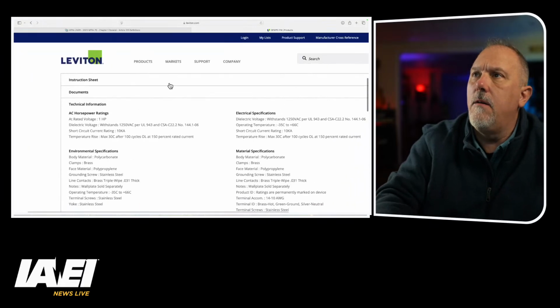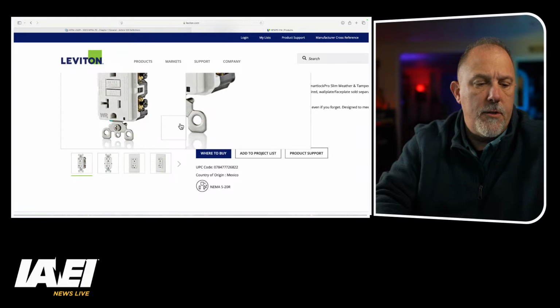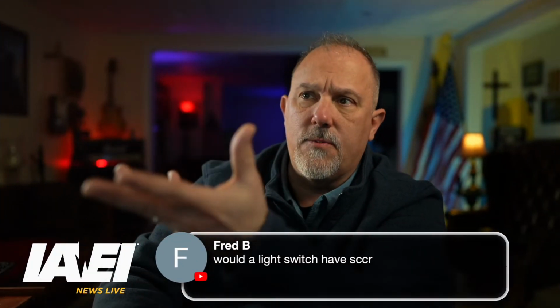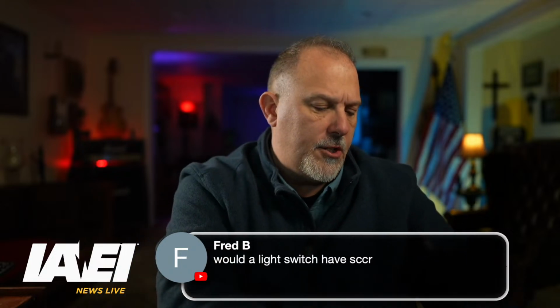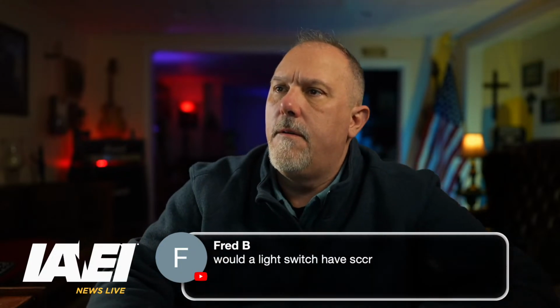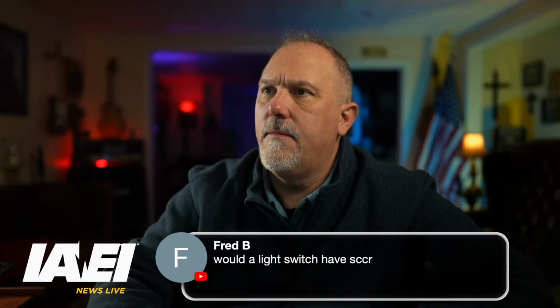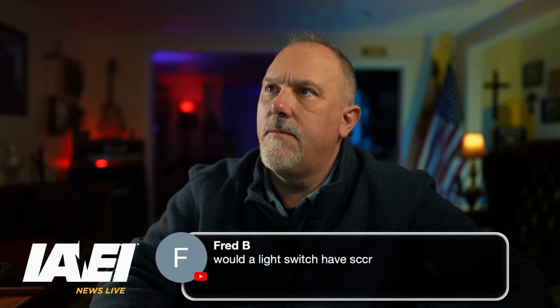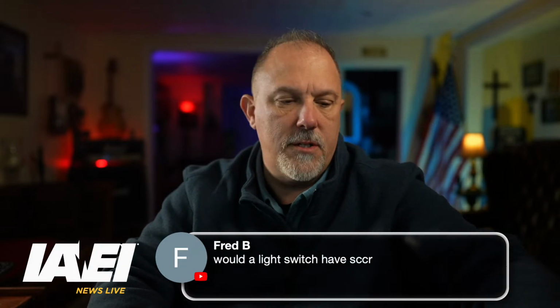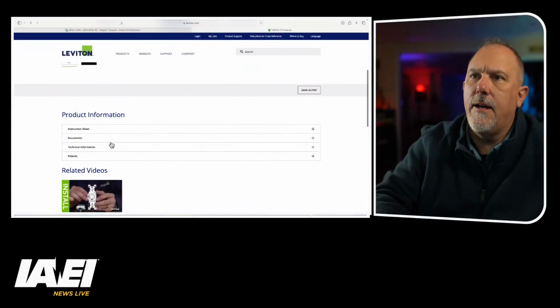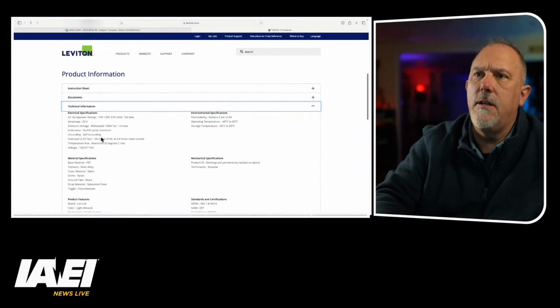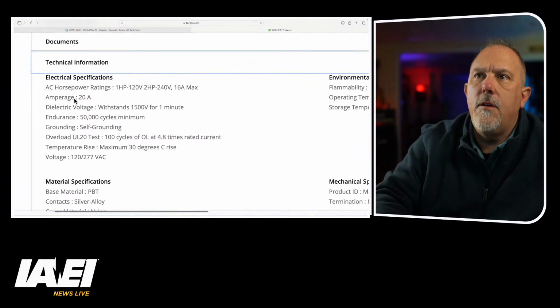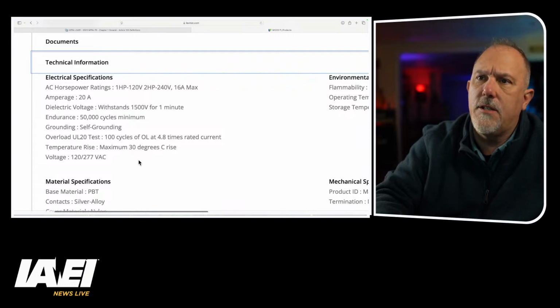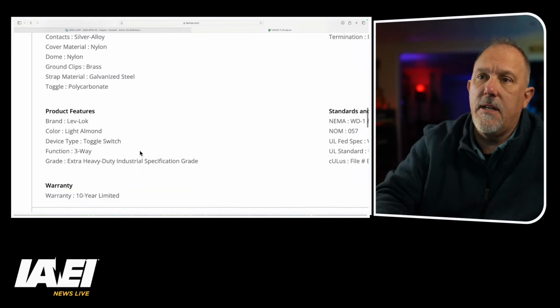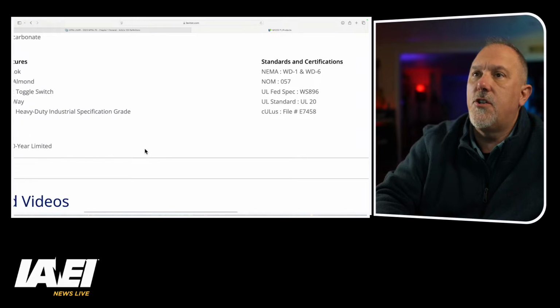And you have horsepower ratings as well. So that shows you that there's at least one manufacturer. Let's take a look at a light switch. Here we go. Toggle switch. They call them toggle switches. So let's take a look down here. Let's go to instruction, technical information. Ampere, withstand 1500 volts for 1 minute. Grounding, overload, temperature rise, voltage. I'm not seeing anything in here on short circuit current rating.